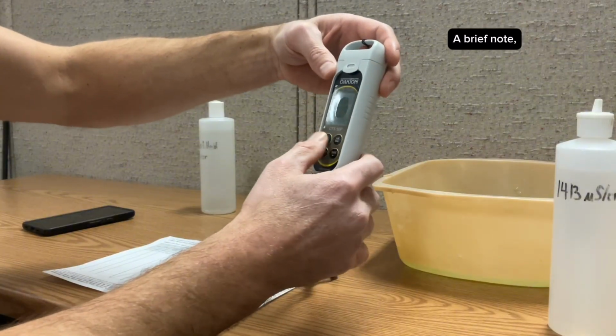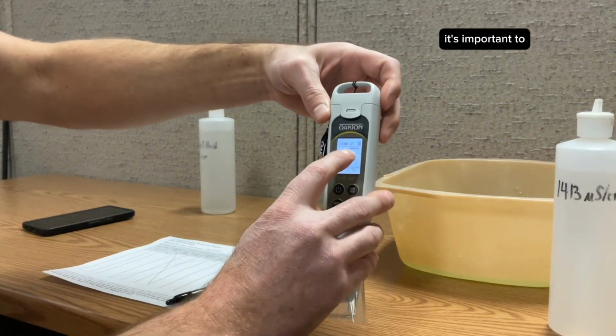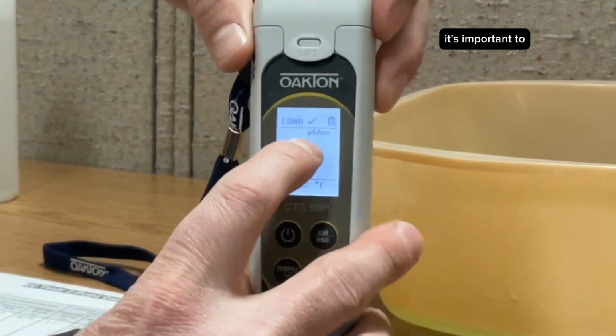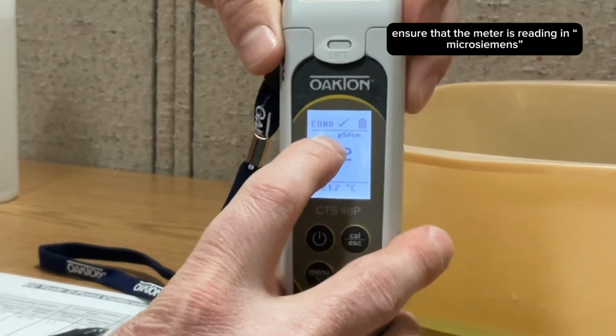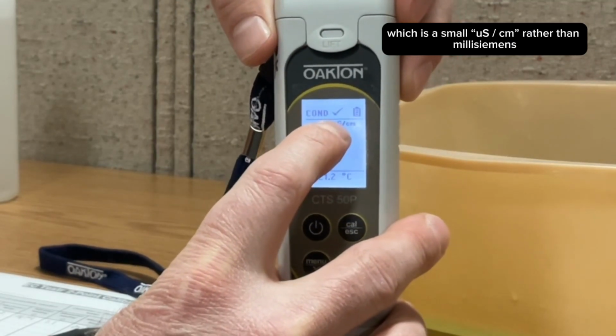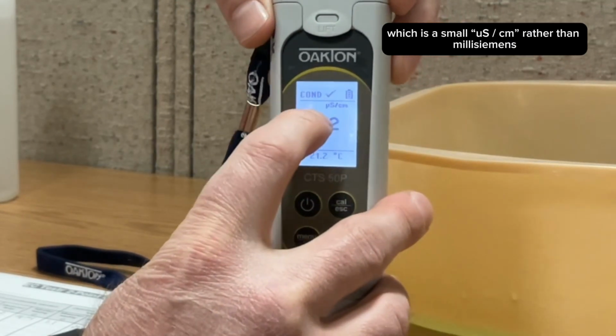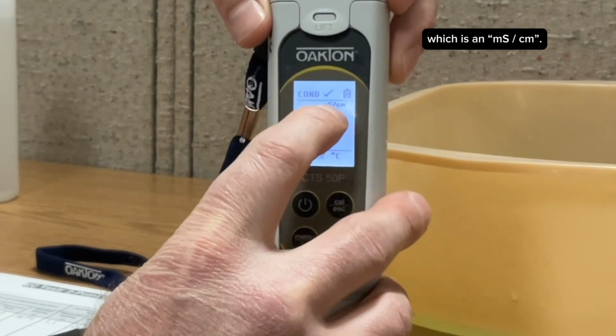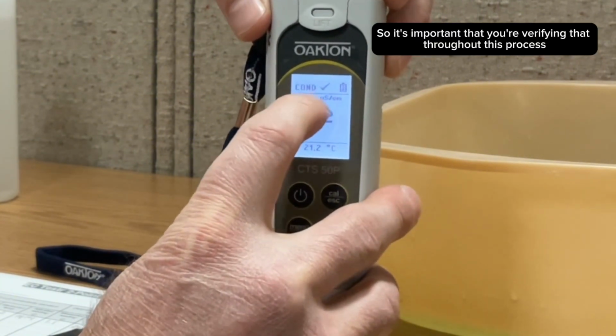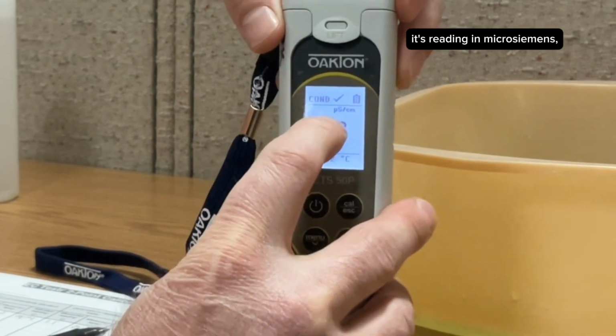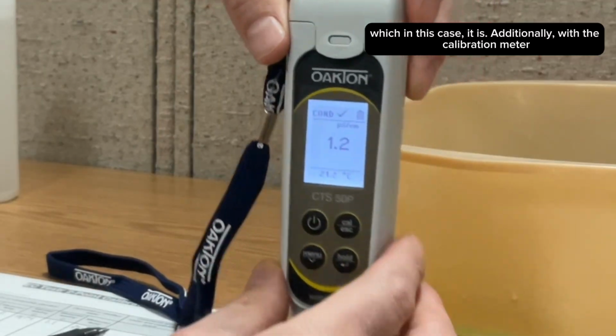A brief note, throughout the calibration process, it's important that you ensure that the meter is reading in microsiemens, which is a small µS/cm, rather than millisiemens, which is an mS/cm. So it's important that you're verifying that throughout this process, it's reading in microsiemens, which in this case it is.